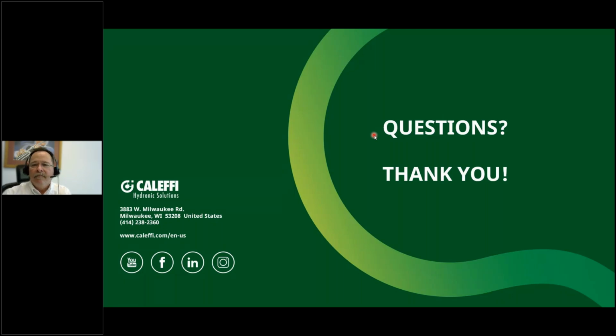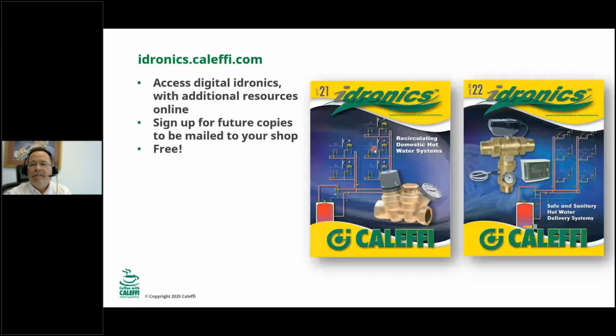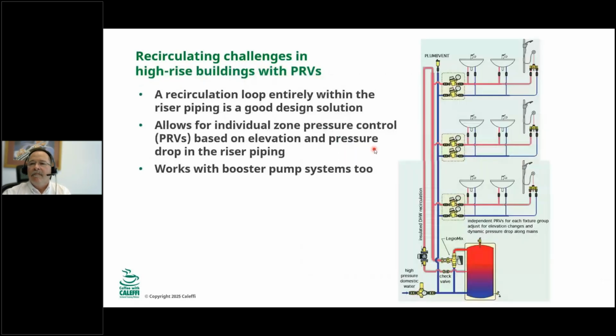A couple that may help: go back a few slides, to the one with the high-rise building. Back, yeah, right there. The question was, same scenario, but let's say the water heater is at the top of the building in a penthouse mechanical room, with booster pumps at the bottom. Would you change anything major with this drawing? No. If that's a top feed or a bottom feed, as long as you're recirculating on the high pressure side of the PRVs, it's basically the same.